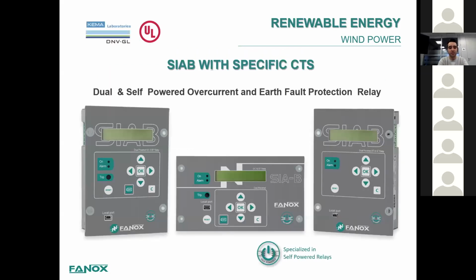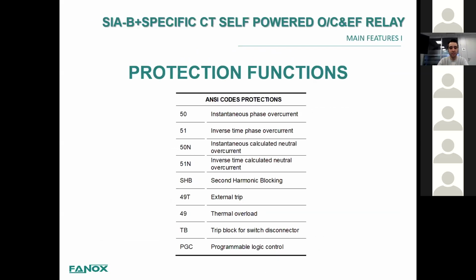The first one is our SIA-B with specific CTs. We have different mechanical adaptations, horizontal or vertical, depending on what your requirements in terms of size are for your circuit breaker. And as you can see here, these are the main protection functions. We have overcurrent, earth fault current, an external trip and thermal overload, and also second harmonic blocking, as well as trip block, and if necessary, some logic that can be achieved during the configuration of this relay.